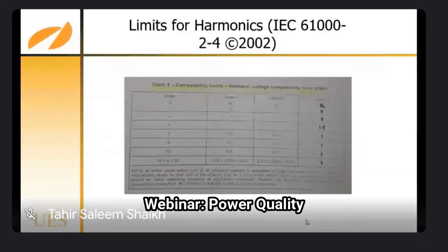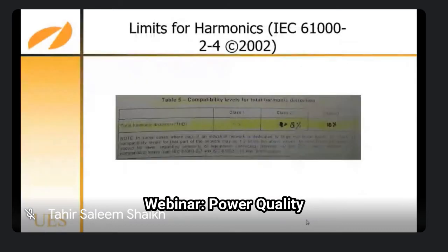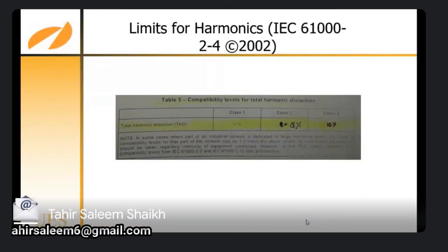Compatibility levels, harmonic voltage components, even order, that is not of much importance for the process industry. Now you can see the total harmonic distortion over here. For class 1 it should be less than 5%, class 2 it should be 8%, and class 3 it should be 10%.